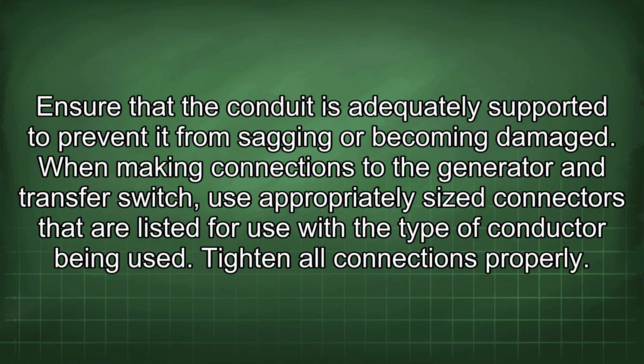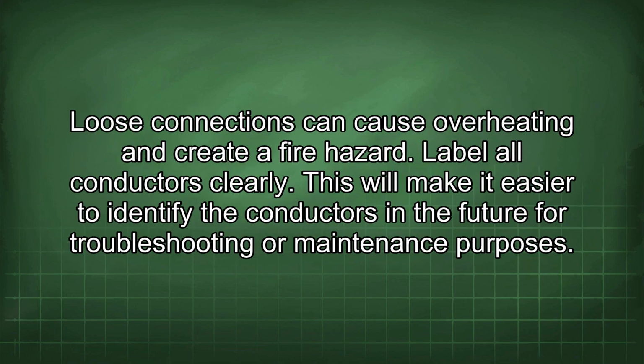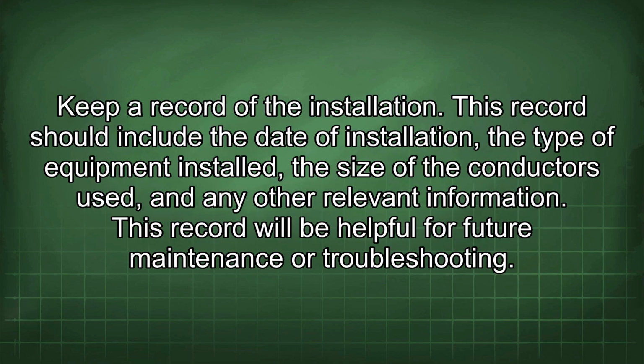When making connections to the generator and transfer switch, use appropriately sized connectors that are listed for use with the type of conductor being used. Tighten all connections properly. Loose connections can cause overheating and create a fire hazard. Label all conductors clearly. This will make it easier to identify the conductors in the future for troubleshooting or maintenance purposes. Keep a record of the installation. This record should include the date of installation, the type of equipment installed, the size of the conductors used, and any other relevant information. This record will be helpful for future maintenance or troubleshooting.